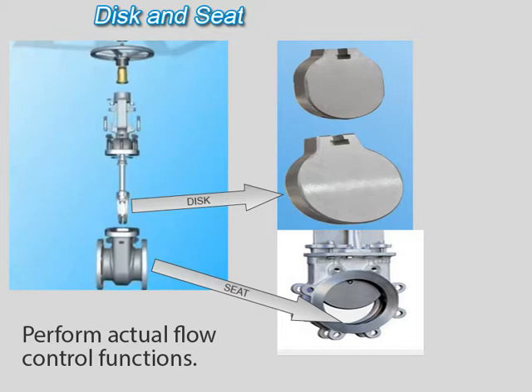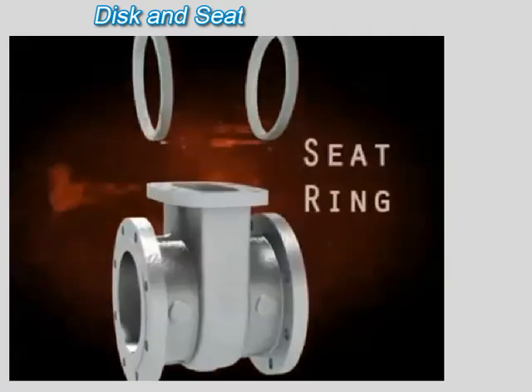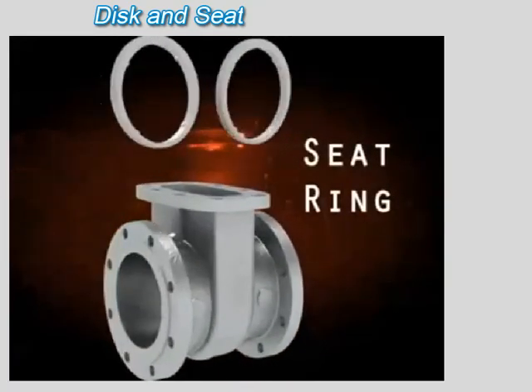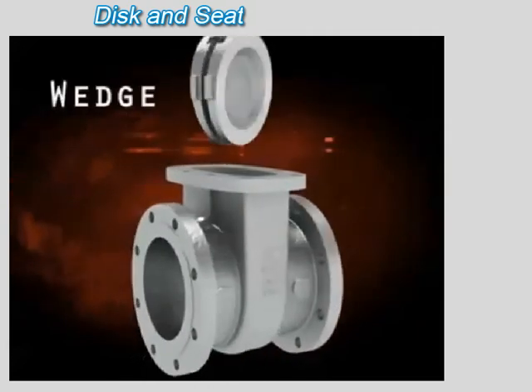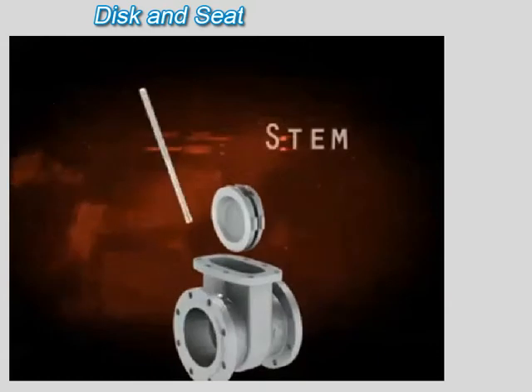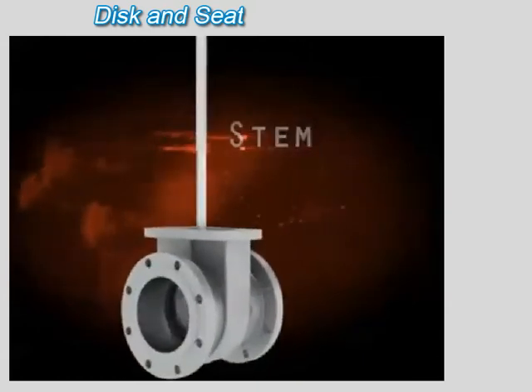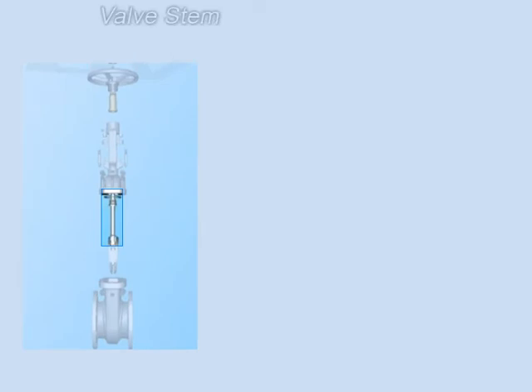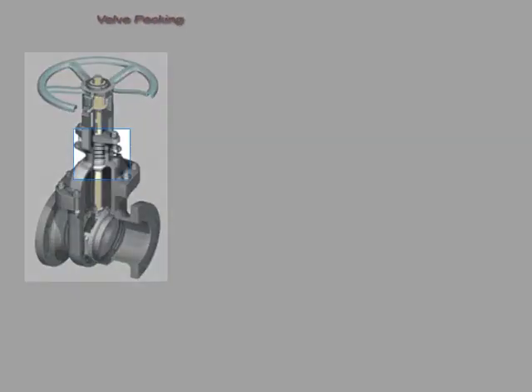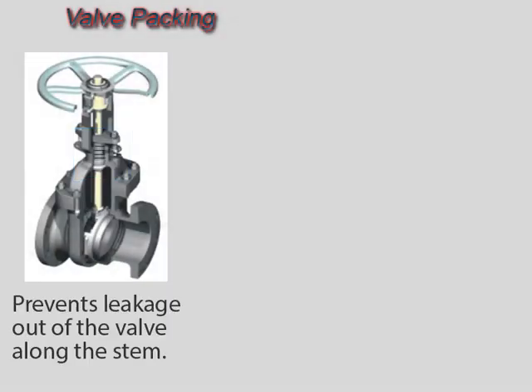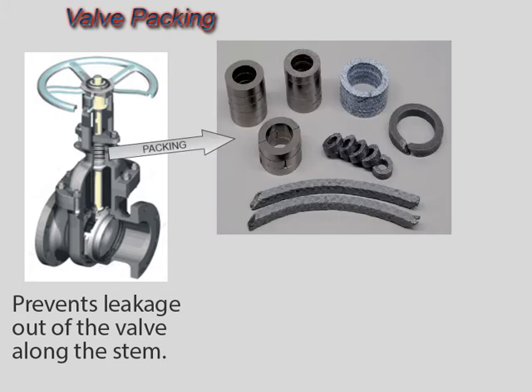Most valves are named in part according to the design of their disc. The stem is the portion of the valve trim that positions the disc. Valve designs typically require stem packing or sealing to prevent leakage, so a fine or smooth surface finish on the stem in the area of the seal is necessary. Most valves use some sort of packing to prevent leakage from the space between the stem and the bonnet. Packing is commonly a fibrous material such as flax, or another compound such as Teflon or graphite, that forms a seal between the internal parts of a valve and the outside where the stem extends through the body.